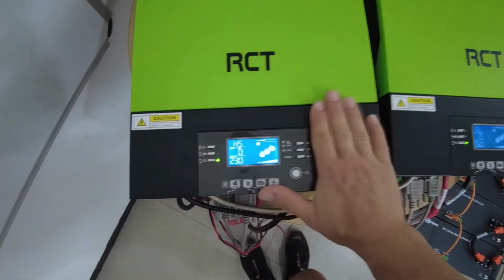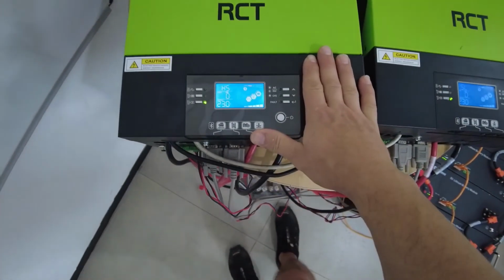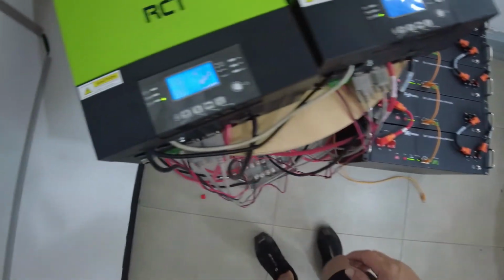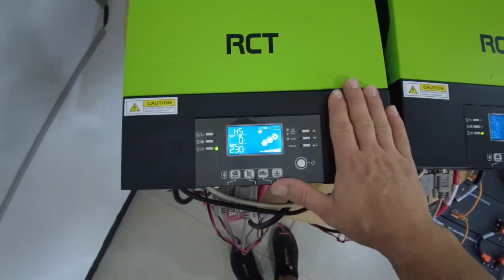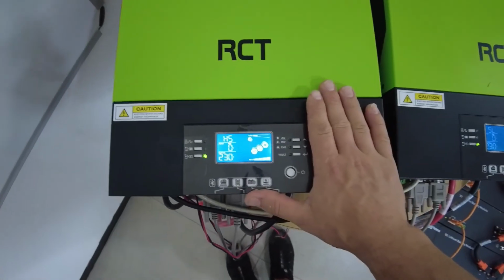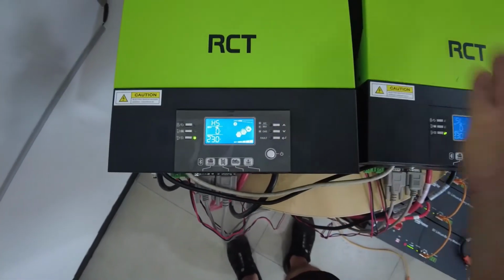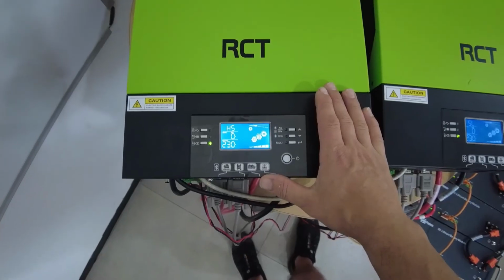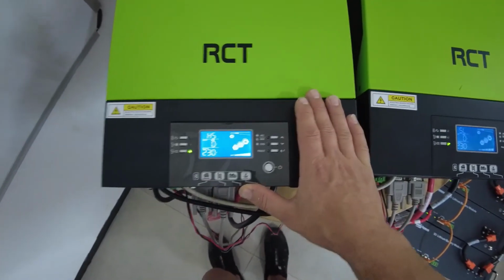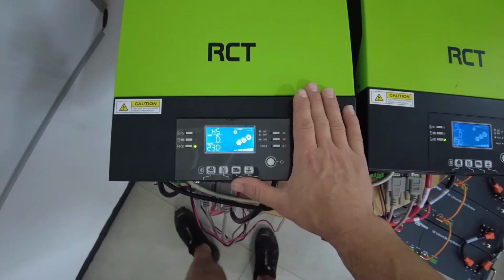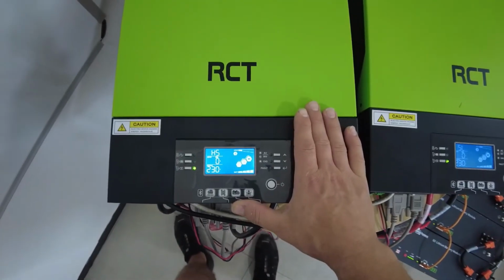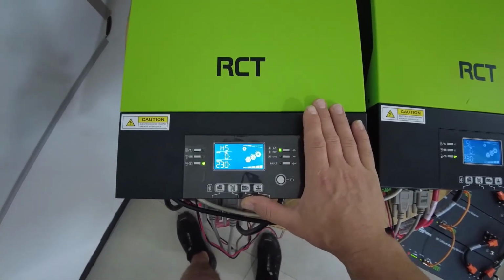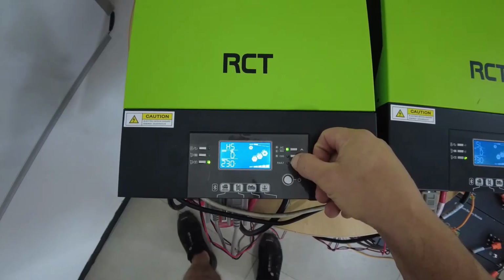Okay, now coming to the master, this inverter will not be connected to the batteries. Now, even though it is the master, like I've said, it's not necessarily always going to be the master. It will change depending on how these inverters shut down and switch on again. Normally the first inverter that comes on after a complete shutdown will be your master inverter. Press enter.